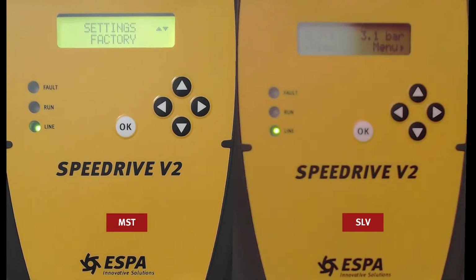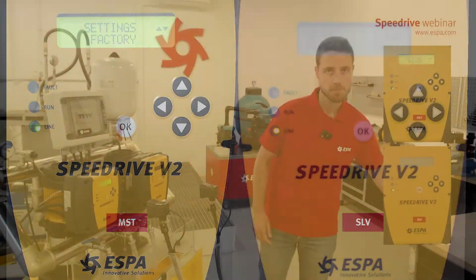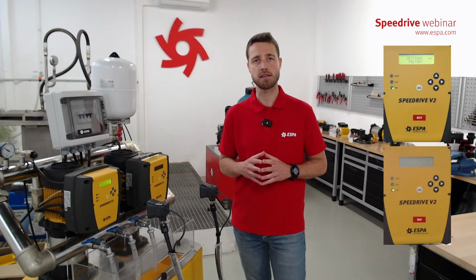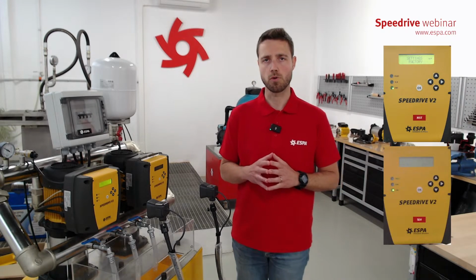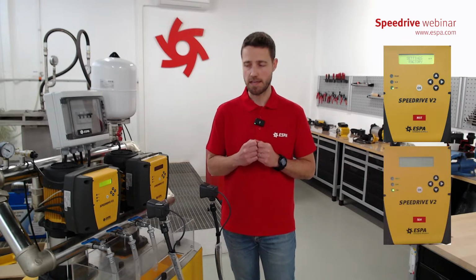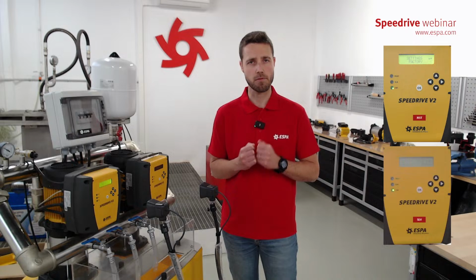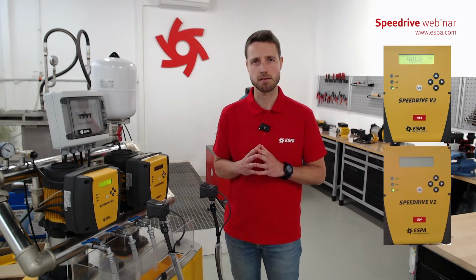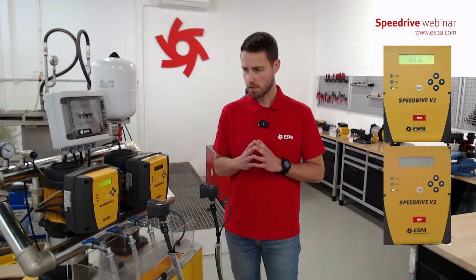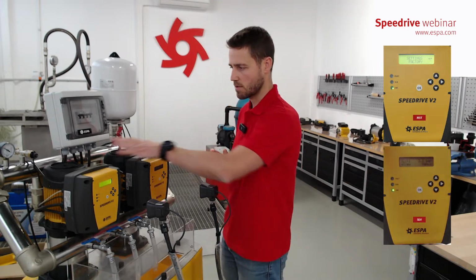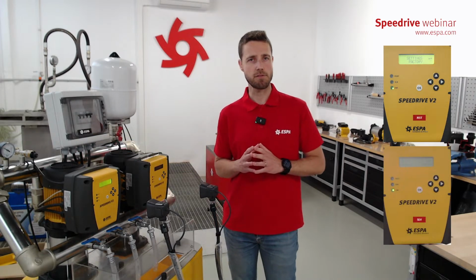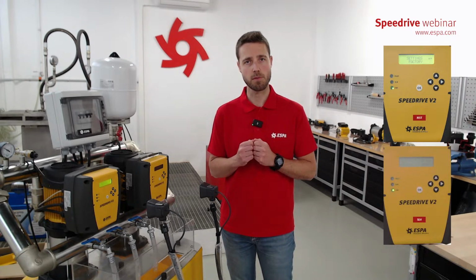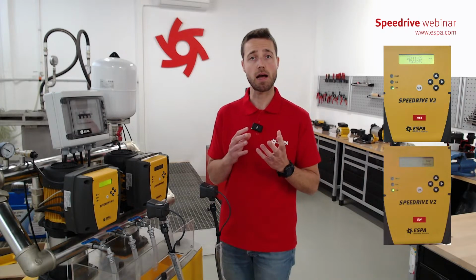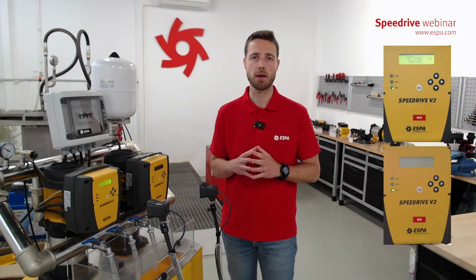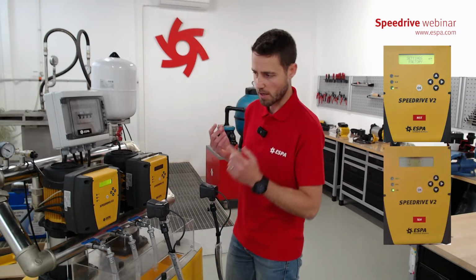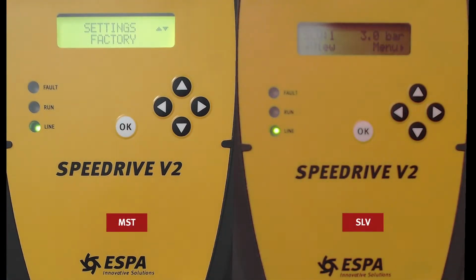Let's continue. Factory settings. Okay. In the case that we have been changing the settings or parameters and we don't remember how it was before, we can go back to the initial configuration. But you have to keep one important thing in mind. Factory settings are always the same. What I want to explain right now is that, for example, the pumps of this booster set are a multi 25-4, but the factory settings come from a multi 35-6. So if we reset, we will have to check the 2 or 3 main parameters of each pump and introduce them properly.